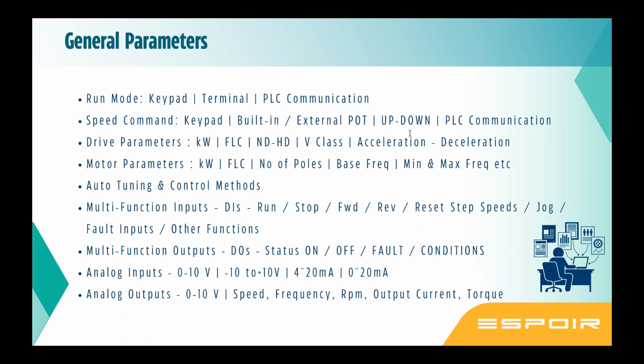What are the options available for a particular model and a particular make? You can choose within the choices given to you. In general, you get 5 digital inputs, 4 as a minimum from any basic drive. Out of that, 1 or 2 are generally defined for run or stop, or forward or reverse. So you have 2 or 3 external inputs. You can use step speeds, you can use jog. I recommend you go through the manual for a very detailed understanding of these aspects.